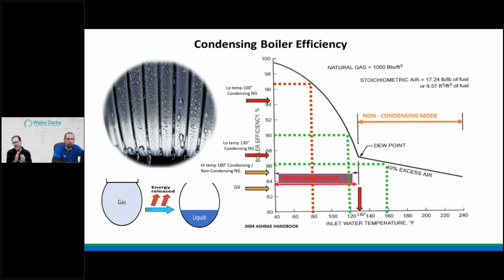That's what we want to achieve by lowering water temperature, or approaching that 130 and less. That's when we're going to reabsorb and take advantage of all of that collapsing flue products back to a liquid, crossing over that heat exchanger, reclaiming the BTUs that would normally leave. Again, the chart's a little similar to the one prior. You see the right, you see the left, condensing, non-condensing. You see inlet water temperatures down at the bottom, and I put a red arrow where it says 130 degrees.